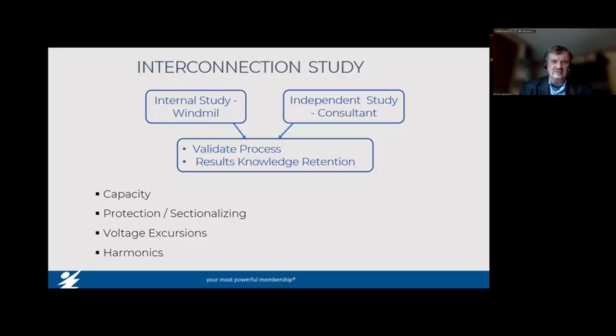And I thought, well, how are we going to manage this? For you engineers, think about this: you have a lot of power being dispatched from batteries and solar at the same time onto the tail end of a distribution feeder. So that power is going to reverse feed the feeder back to the substation, and the substation voltage is regulated. So what that's going to do is push the voltage too high out at the solar plus storage site. So we use some capabilities in the inverters to do what's called VAR compensation, using reactive power, consuming reactive power from the grid in order to control voltage. For those of you who aren't engineers, I'm not going to go into the physics of that, but for those of you who are, and if you understand reactive power, you might have some understanding as to how that worked.